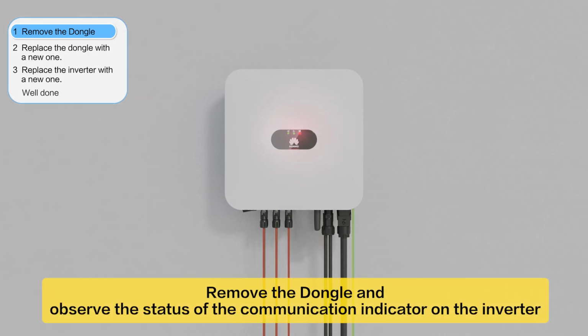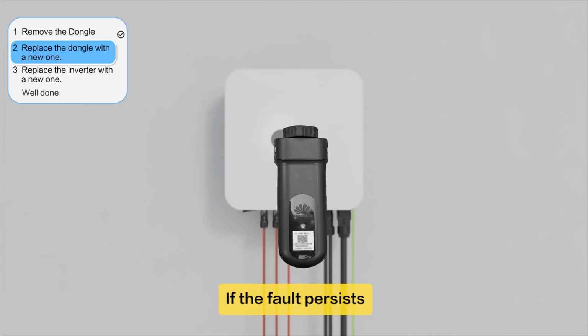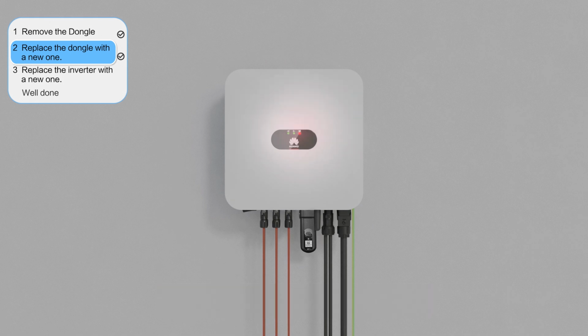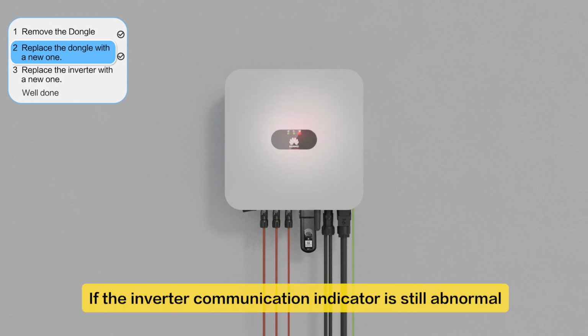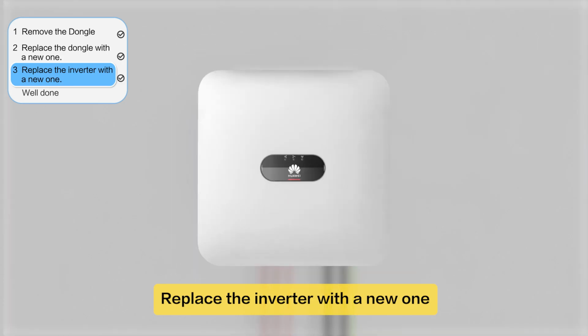Remove the dongle and observe the status of the communication indicator on the inverter. If the fault persists, replace the dongle with a new one. After the dongle is replaced, if the inverter communication indicator is still abnormal, replace the inverter with a new one.